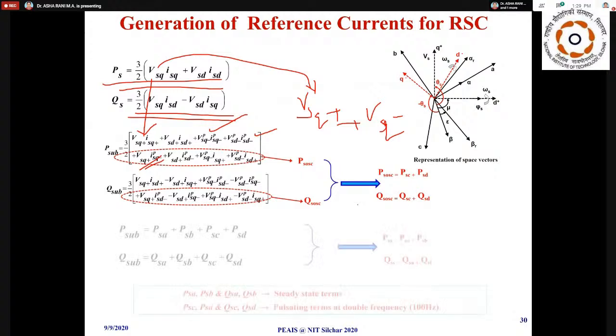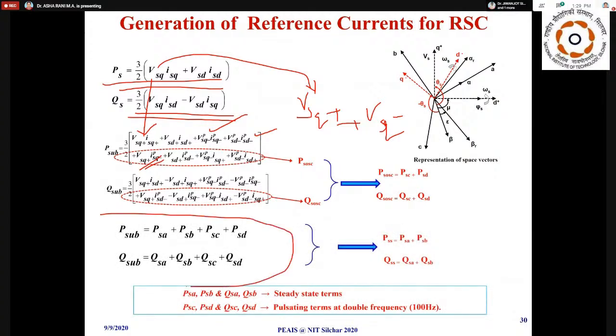So we definitely have to eliminate those elements, otherwise it will be disturbing the machine and your machine winding will go. And when you are continuously running that, this will inject harmonics into the grid, which is also not allowed. So we have to take measures.